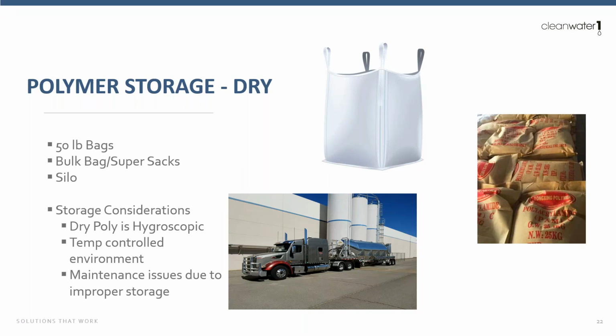Other storage considerations for dry polymer. Dry polymer is extremely hygroscopic, meaning it attracts water very, very easily. We want to keep these bags in a temperature controlled environment and preferably a humidity controlled environment as well. If that polymer is fouled due to excess moisture or improper storage, maintenance issues definitely can occur, right? We can see clumping, we can see feed issues, and then you're also not going to get effective wetting and activation out of that polymer itself. So keeping these dry polymer bags in a climate controlled environment is really, really important for the overall process and maintenance.